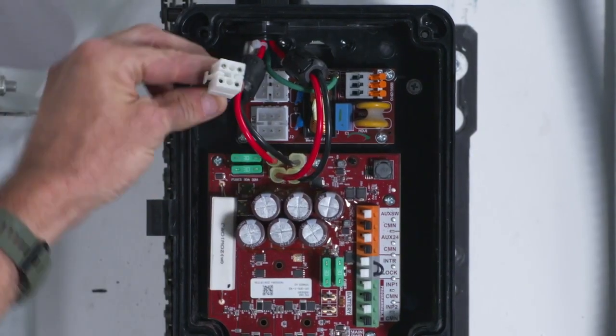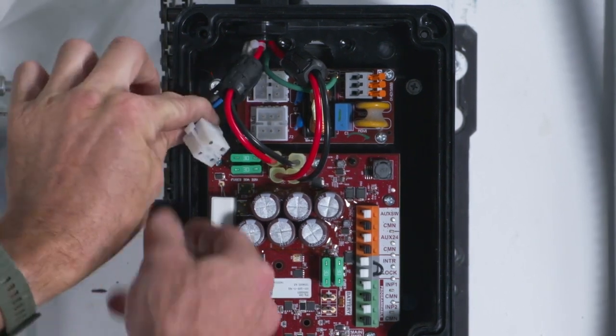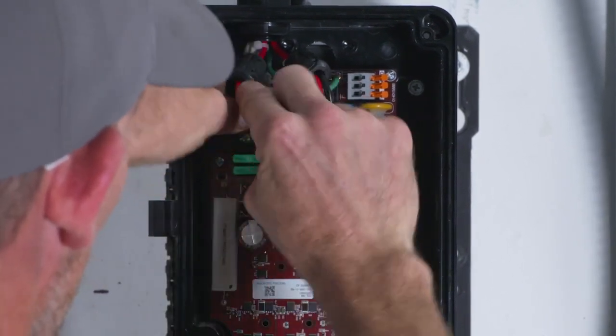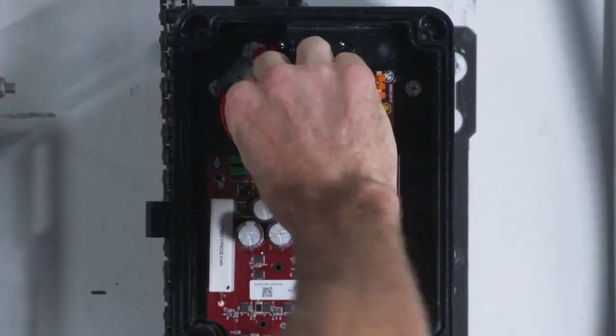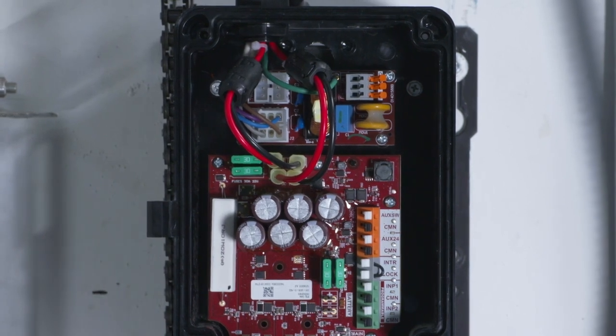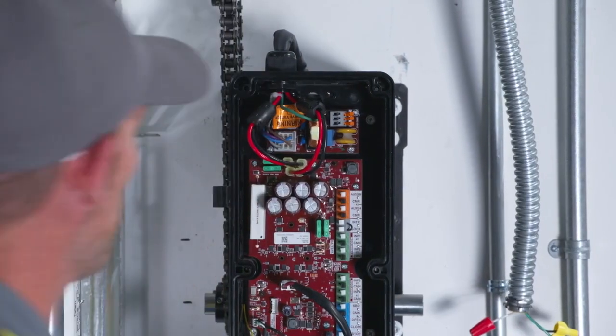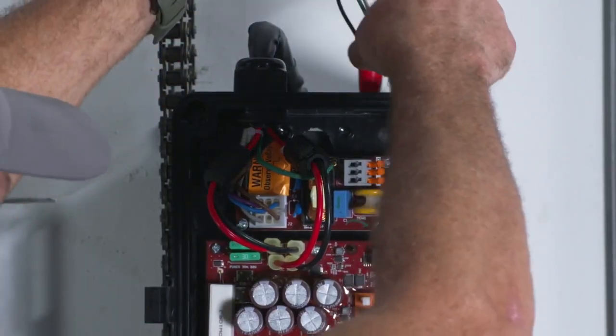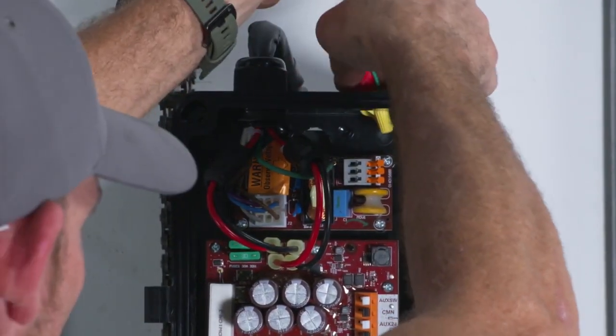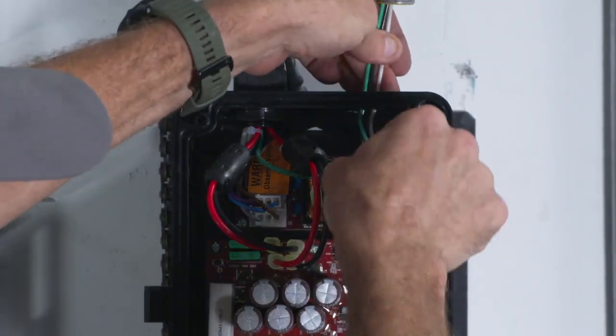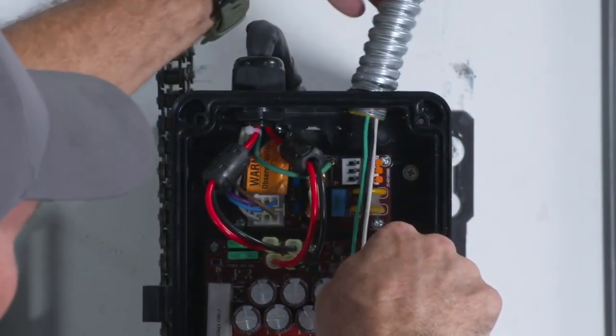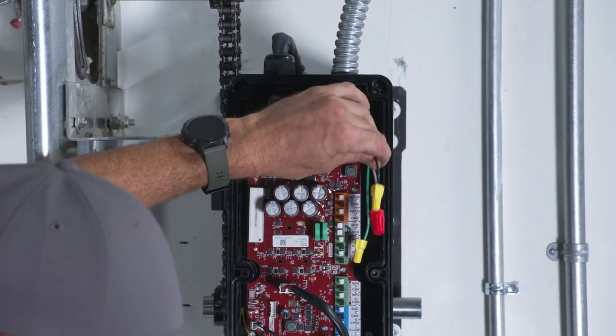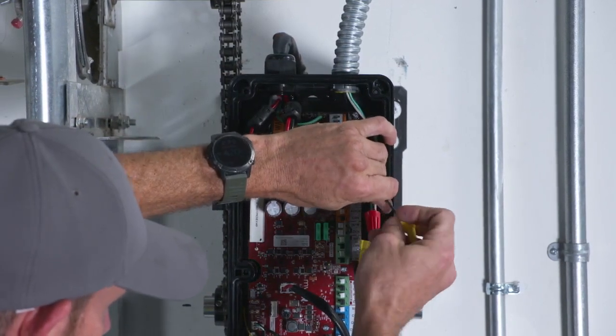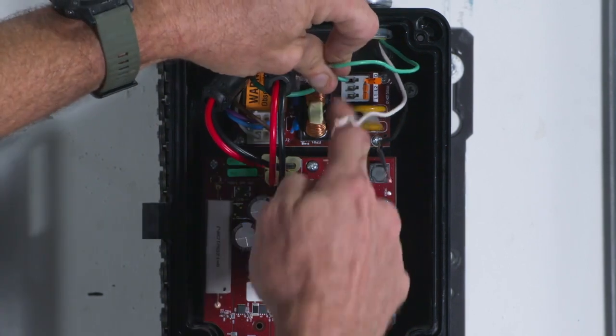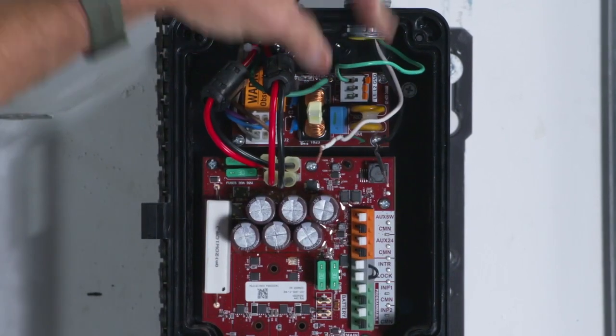Identify the connector for your application's voltage. For this demonstration, we are connecting to 120-volt single-phase power. Plug the power selection wire harness into the connector. Make sure it is securely snapped into place. Cover the unused connector with the label. Route the power wiring into the operator. Then secure the conduit to the power head. Locate the connectors labeled L1, L2, and ground. Plug the appropriate power wires to those connectors using the new Easy Push tab plugs.